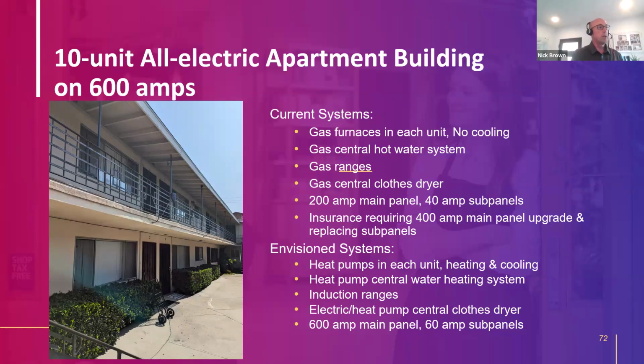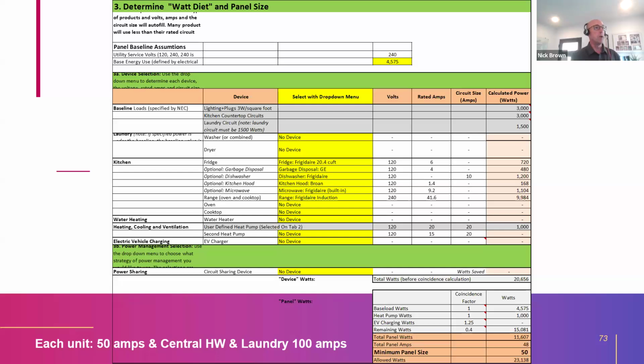We're planning to install a ductless mini split in each unit, a central heat pump water heater, probably a couple of 80 gallon tanks for the whole building, we'll have to run some calculations on that, induction ranges, and replace the current gas dryer with an electric version. We think we can get this done with a 600 amp main panel and 60 amp sub panels, which isn't a big cost increase from what the insurance company is requiring anyway.